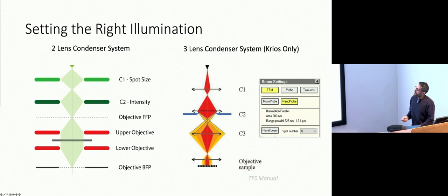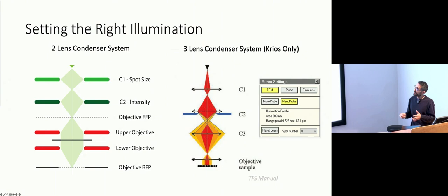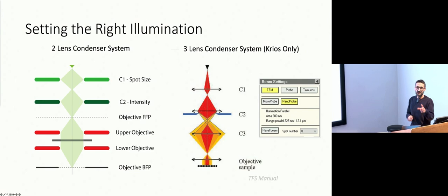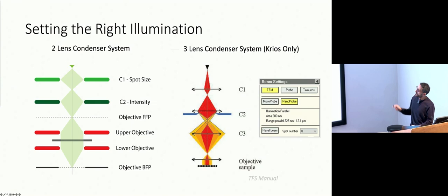The next thing to consider is the optics. Most of the time the facility will have settings already chosen for you; all you need to do is adjust these optics for your experiment. One extremely important setting is parallel illumination. Parallel illumination is achieved by setting the last crossover of the condenser system in the front focal plane of the objective lens, and the last crossover of the objective lens in the back focal plane of the objective lens. When this condition is met, the beam going through your sample is parallel — although the beam is never truly perfectly parallel, it gets as close as it can.